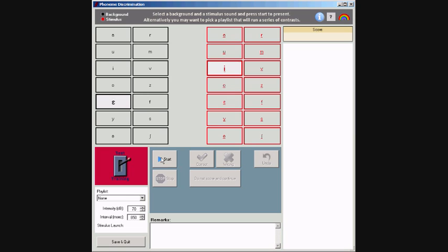The default intensity at which the ACE phonemes are presented is 70 dB HL*. HL* stands for hearing level, with the reference sound being a narrow band noise centered at 1 kHz. Since all phonemes are loudness balanced, this is the correct scientific notation.